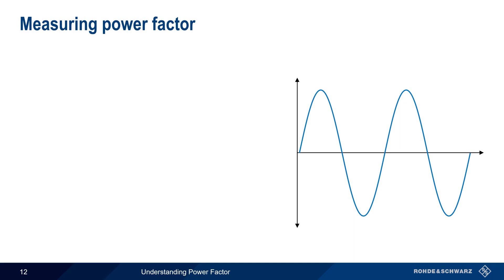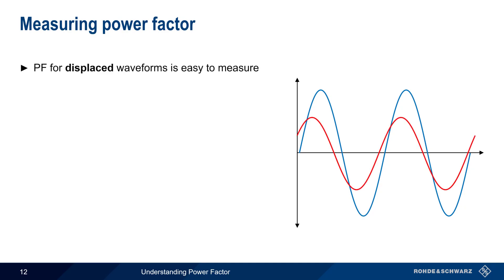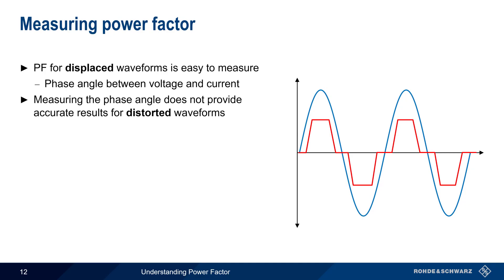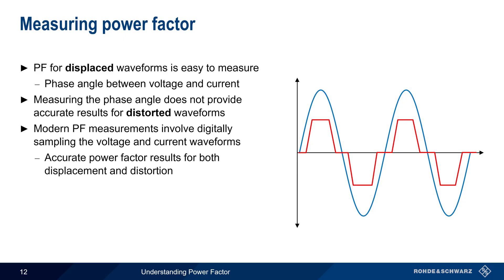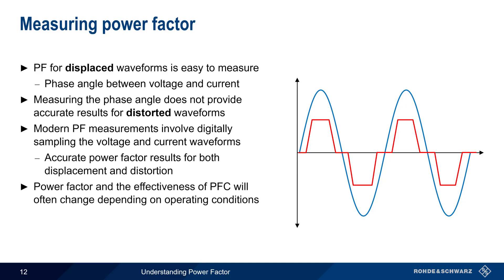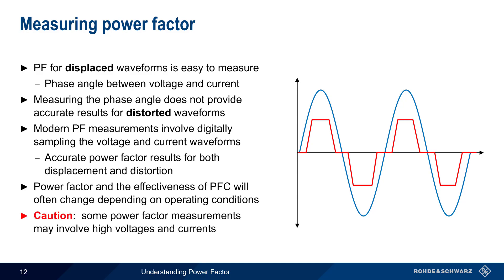So how do we measure power factor and evaluate the effectiveness of power factor correction? It's relatively easy to measure the power factor for displaced waveforms — simply measure the phase angle between voltage and current and take the cosine of this value. However, this approach will not yield accurate results for distorted waveforms, which are often the more common case in modern applications. Therefore, modern power factor measurements usually involve digitally sampling the voltage and current waveforms and using these sampled values to calculate power factor. This provides accurate results for both displacement and distortion. Power factor and power factor correction often change substantially depending on working conditions, so it's important to test under a variety of operating states. Please keep in mind that some power factor measurements may involve high voltages and high currents, and can present a risk to both devices as well as to human operators, so caution is advised.